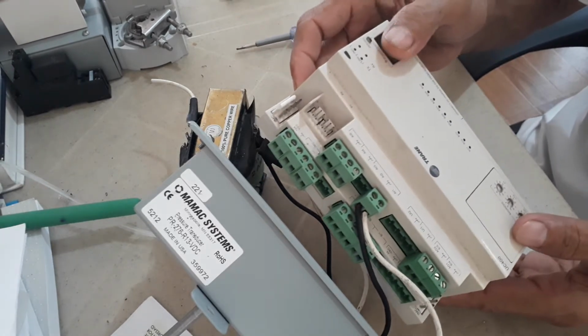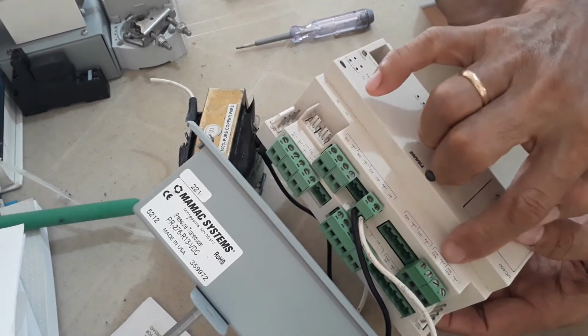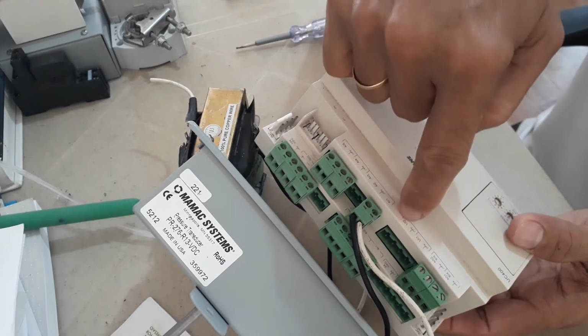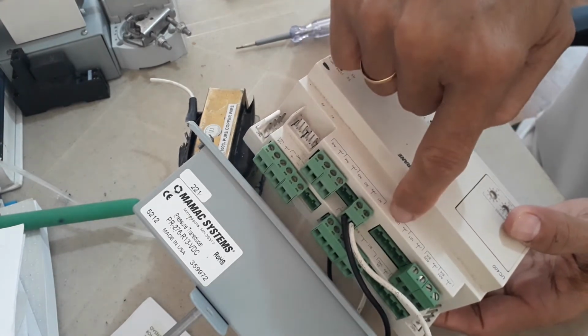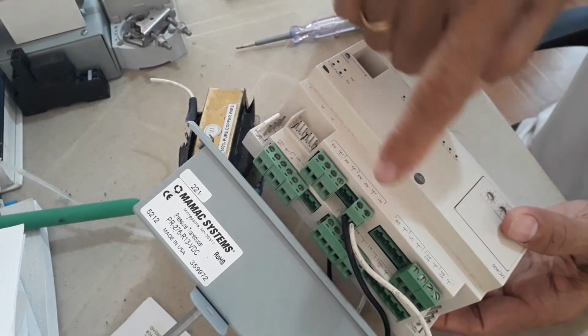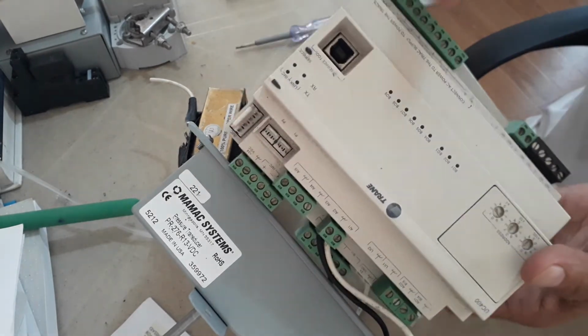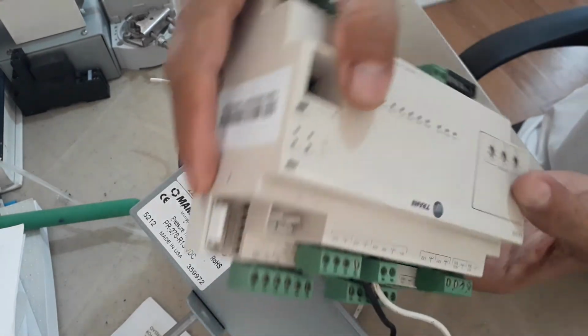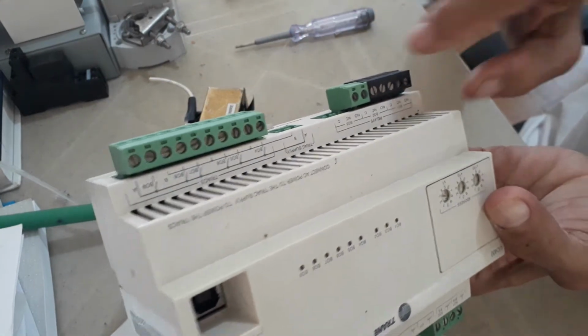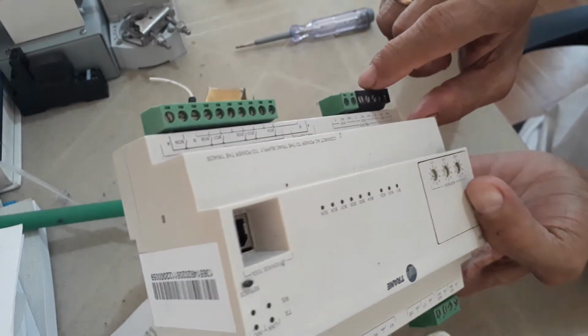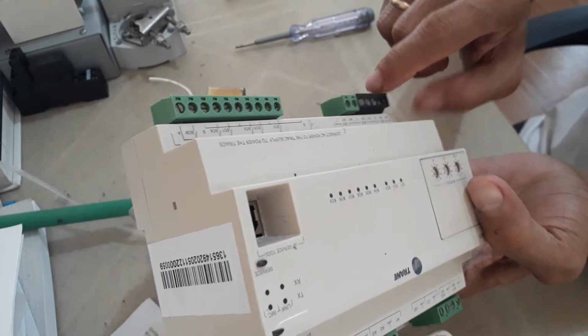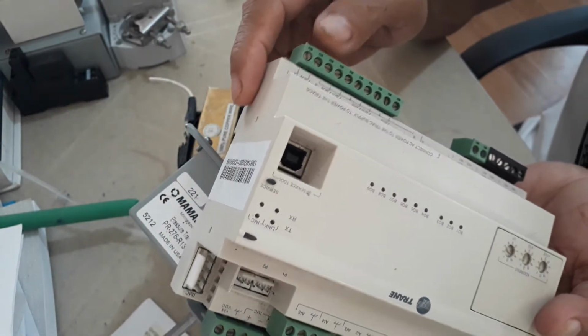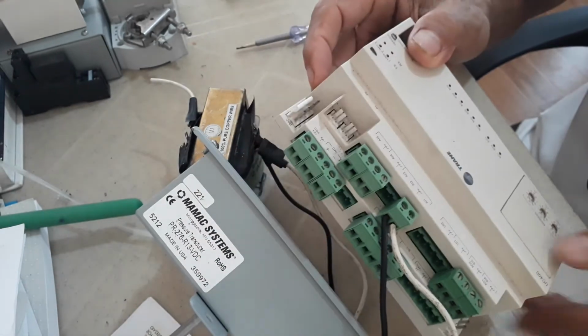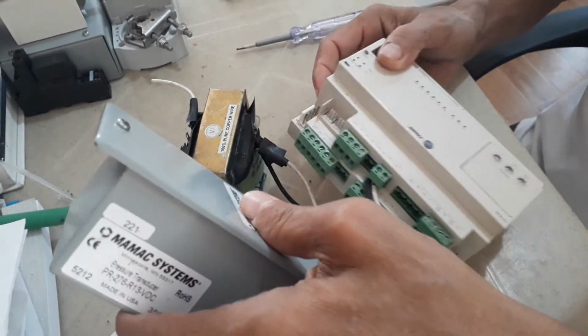Now this controller can provide also analog output. It can accommodate universal inputs, 1 and 2. Analog output 0 and 1, so 2 analog outputs. Then it has also binary outputs here. So these are binary outputs. It has around 1, 2, 3 binary outputs. Then it can provide also triac output. Okay, so this is a very good DDC controller.